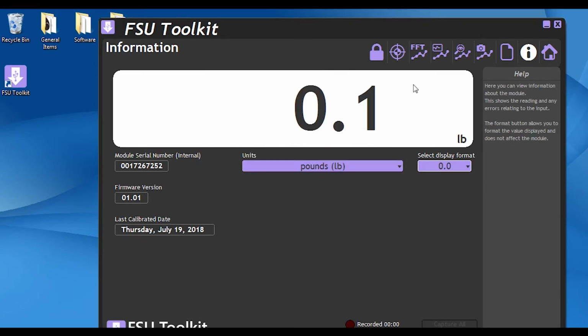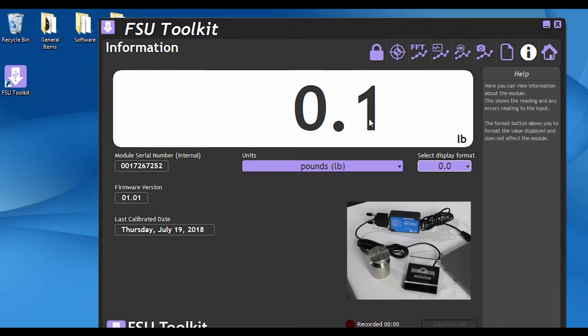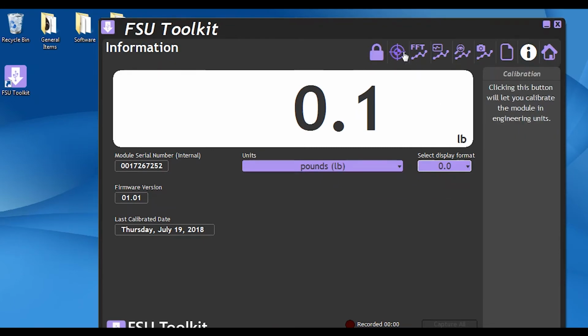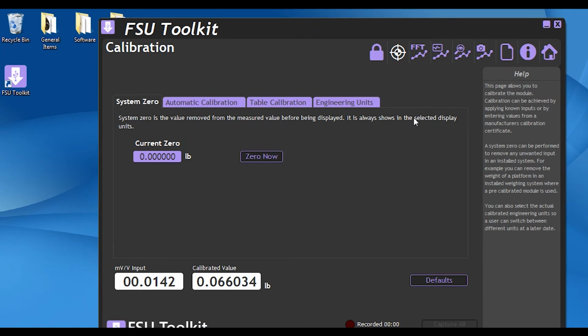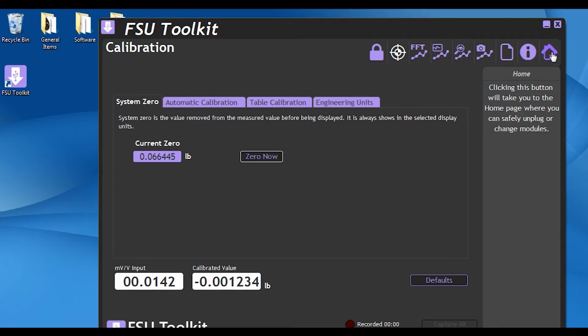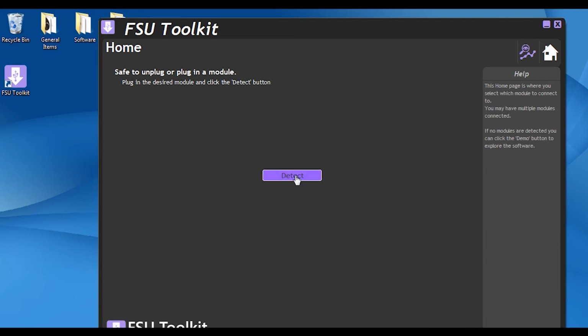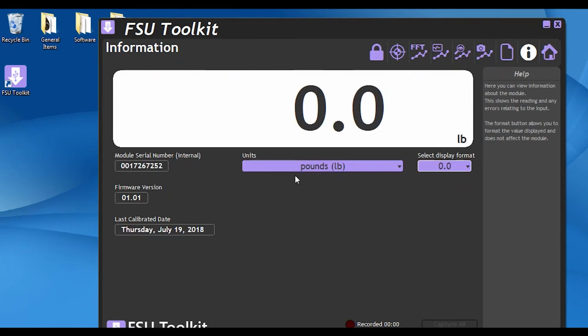And if any number shows on this screen, we'll want to go back and reset the system 0. At this point, we've got 1/10 of a pound showing, and we have nothing on our scale. So what we're going to do is go back to the calibration icon, say 0 now, and then we can go back now to the Home icon and hit Detect, and we should have 0 showing on the screen, and we do.